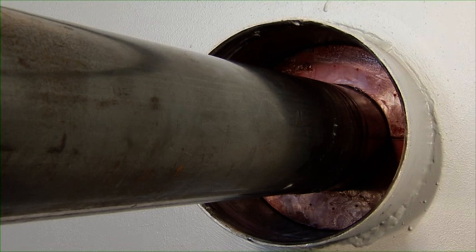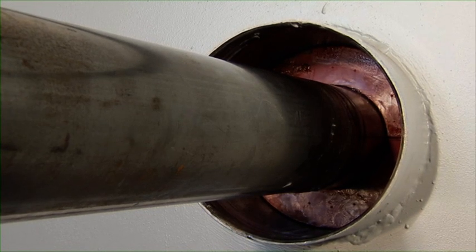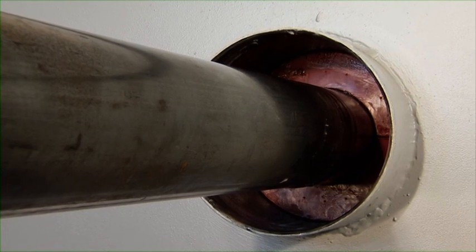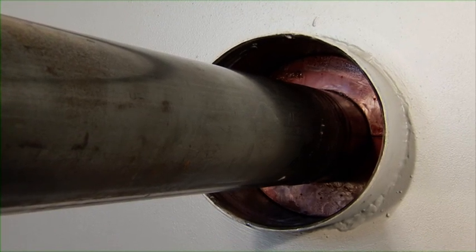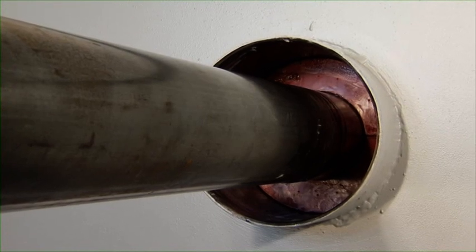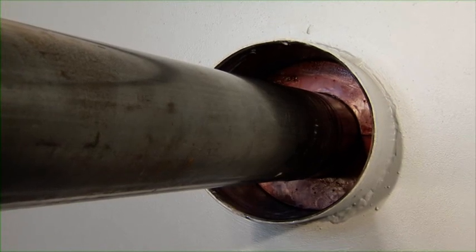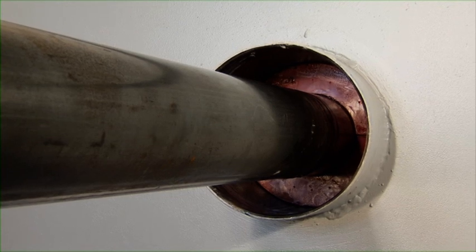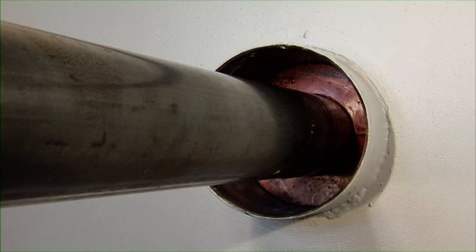For ultimate fire safe and watertight penetrations, the slip sill sealing plug should be installed on both sides of the conduit. Make sure the conduit is ground out to avoid damage to the plug during installation, and remove any dirt, oil residues or welding spots from the conduit sleeve and surface of the service pipe.